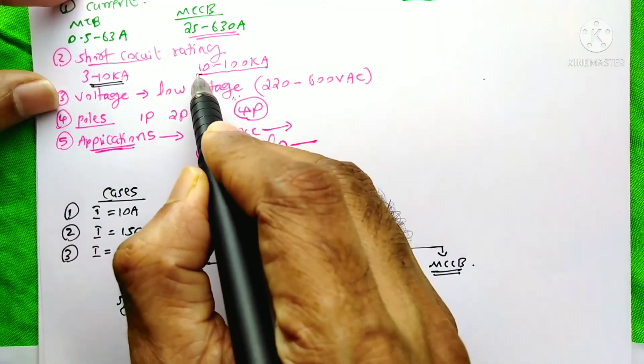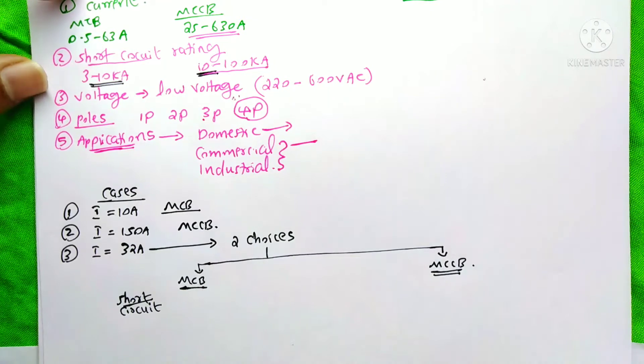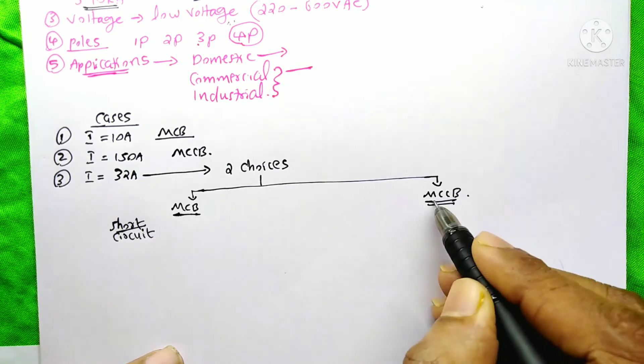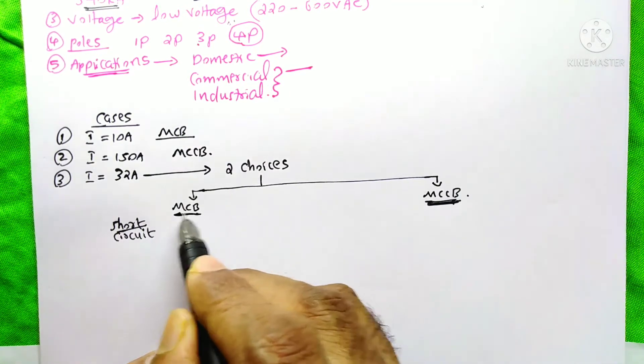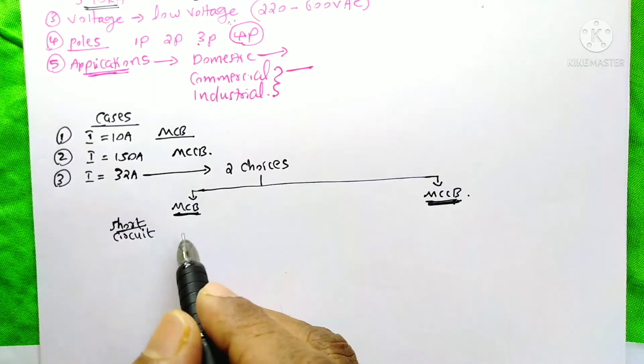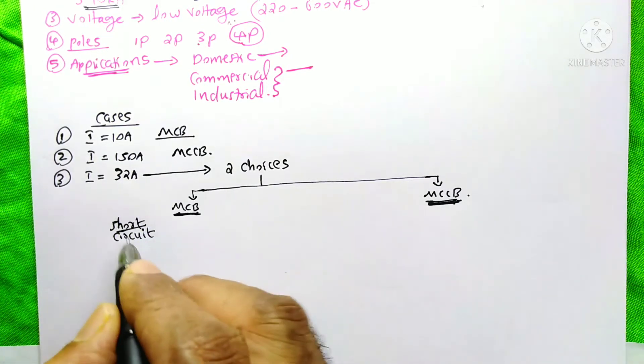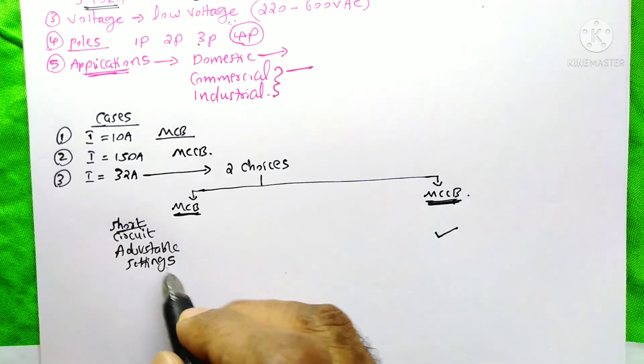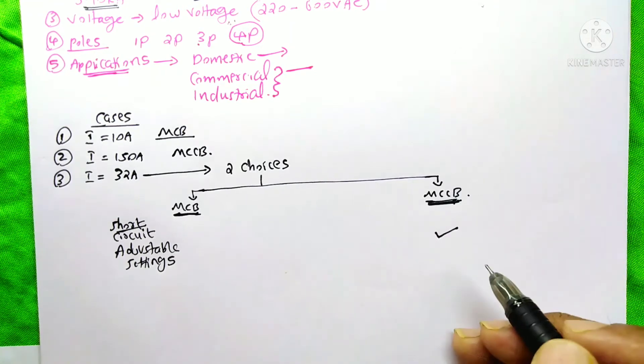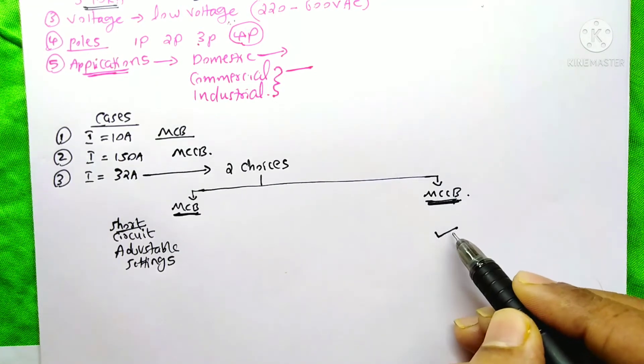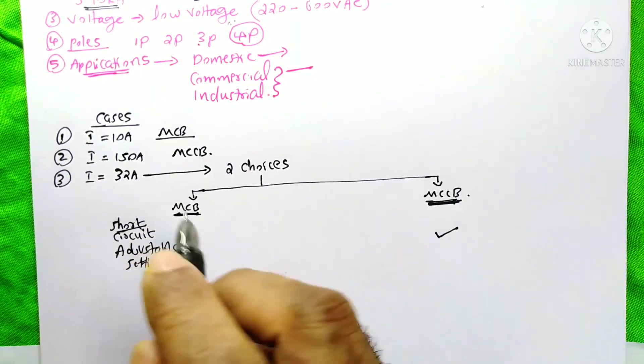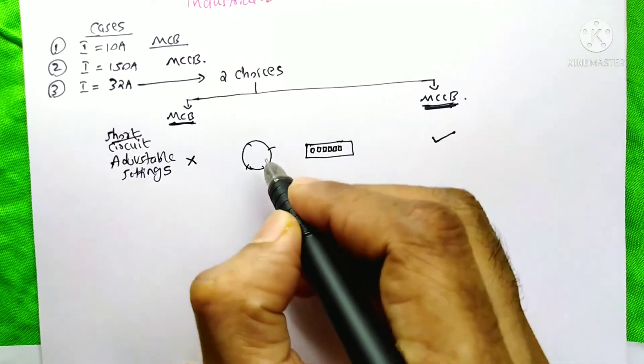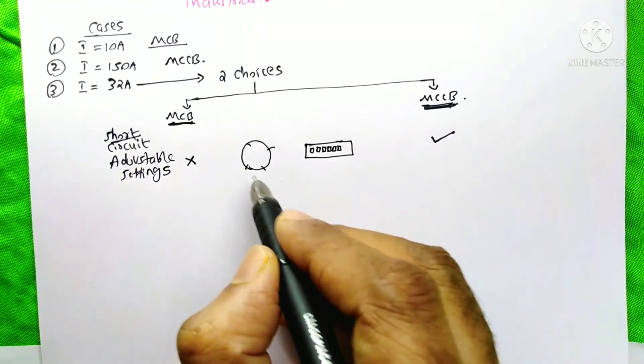If the short circuit current is exactly 10 kilo-amperes, you have two choices, since both the MCB and MCCB offer 10 kilo-ampere ratings. The selection then depends on your budget — if you have enough budget, select the MCCB; otherwise, select the MCB. If your application requires adjustable settings, you must select an MCCB. Adjustable settings allow you to adjust the current settings and the short time current settings on the device, which is not available on the MCB — the MCB is completely automatic.